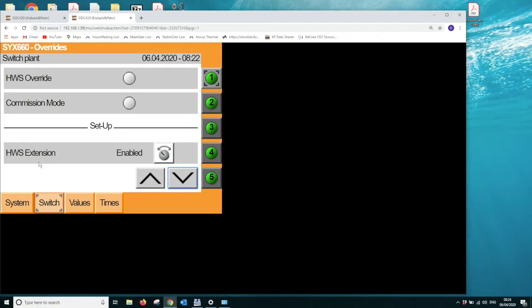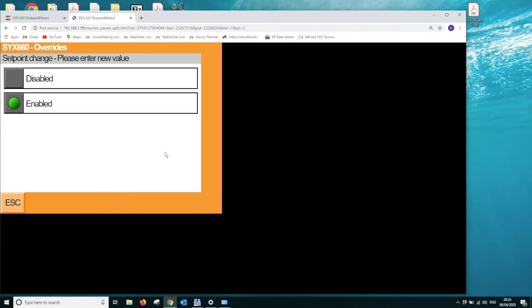So the first option for setup is, do we want to have hot water extension? So this means that the digital input which is used for the day extension timer for the heating system, do we want that also to bring on the hot water system? If we want to have it so that the heating and the hot water are brought on when that button is pressed, then we leave it enabled. If we want to disable it, we can select disabled.